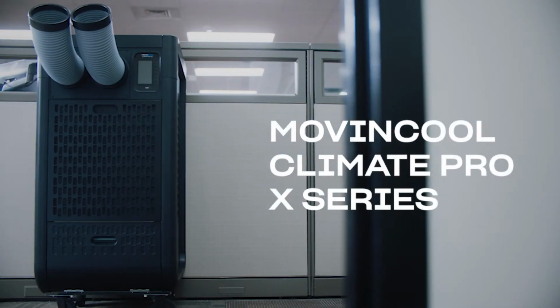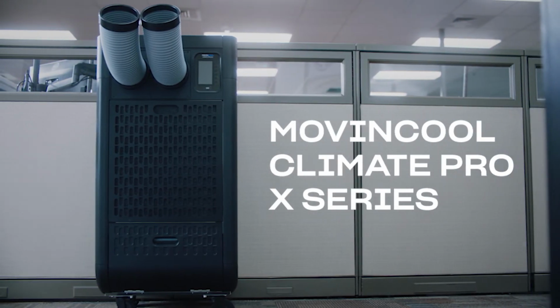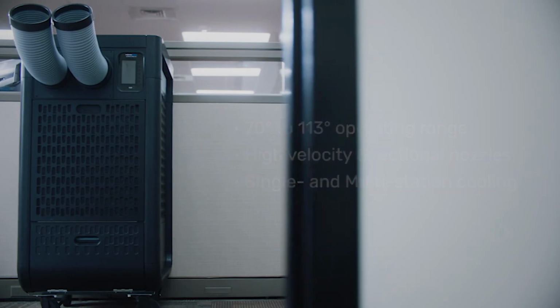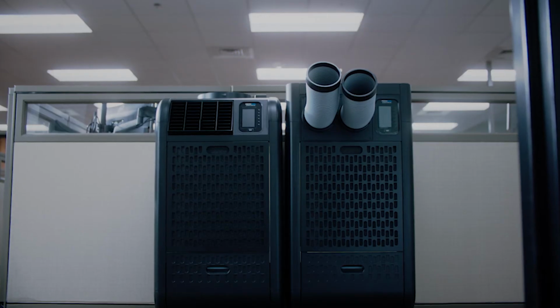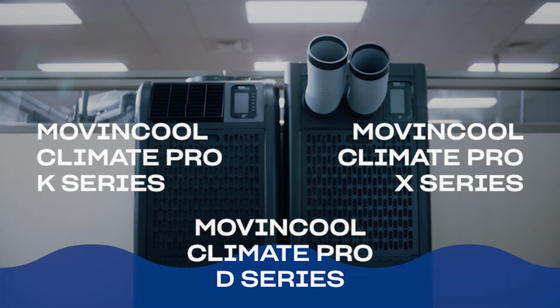MovinCool Climate Pro X Series brings spot cooling to workstations in the hottest environments. Well suited for manufacturing floors, distribution centers, and shipping and receiving bays. Operating range of 70 degrees to 113 degrees. Cool, dry air delivered through directional nozzles at high velocity. Can be configured for dedicated workstations or multi-station cooling. Nozzles are quick connect, twist on, twist off, and can be positioned on the front of the unit as shown, or top mounted. The Climate Pro family of units also includes 1 and 1.5 ton heat pump units.